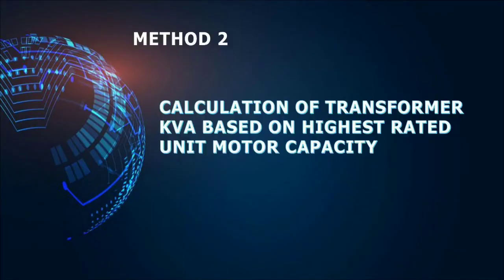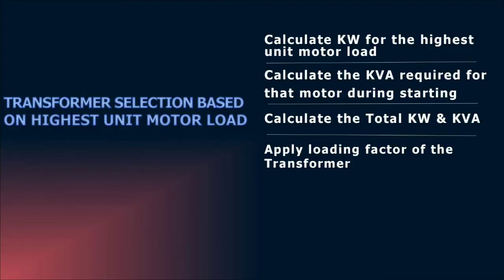Now we are going to see the selection of transformer using the second method. In this method, transformer rating is selected in consideration with the highest rated motor in the electrical system. The steps followed in this method are, we will be calculating the kW rating of the highest rated motor, and from this kW value, we will be calculating the kVA required for that motor during its starting. With these values, we will be calculating the kW and the kVA of the total system, and from that value, we will be arriving at the kVA required for the transformer by applying the percentage loading of the transformer.